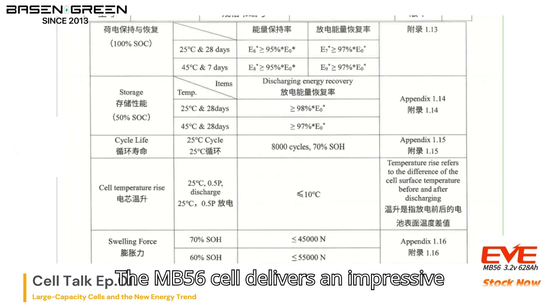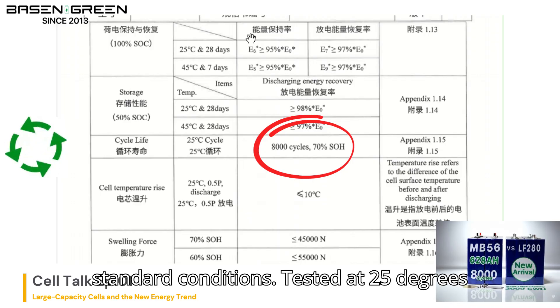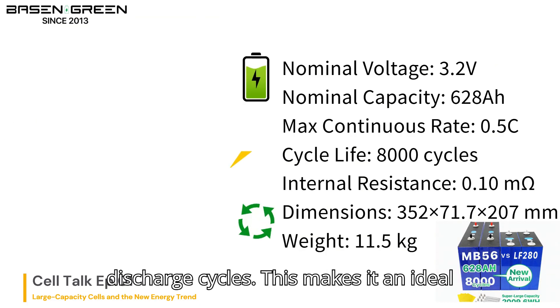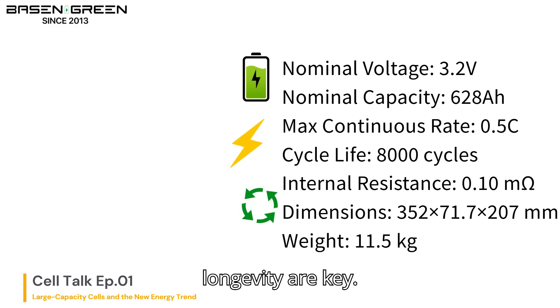The MB56 delivers an impressive cycle life of 8,000 cycles under standard conditions. Tested at 25 degrees Celsius, it maintains 70% state of health even after thousands of charge and discharge cycles. This makes it an ideal choice for long-term energy storage applications where reliability and longevity are key.